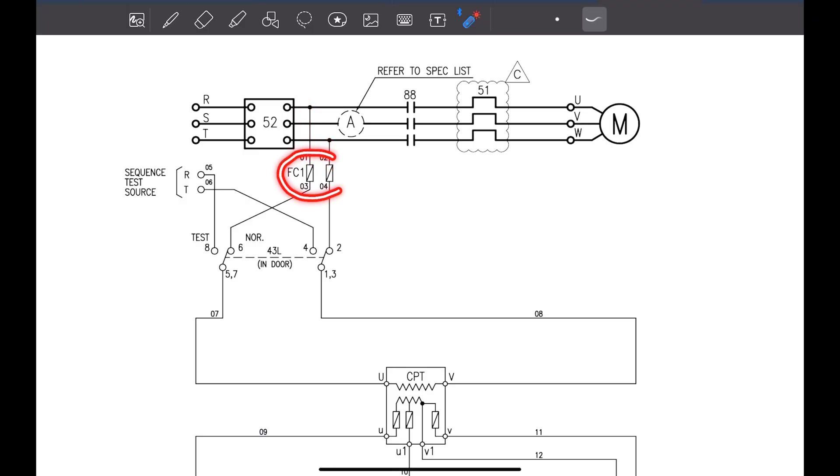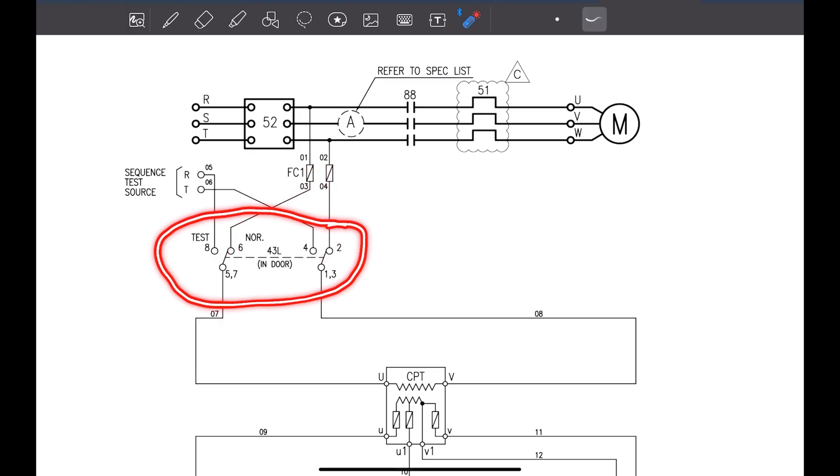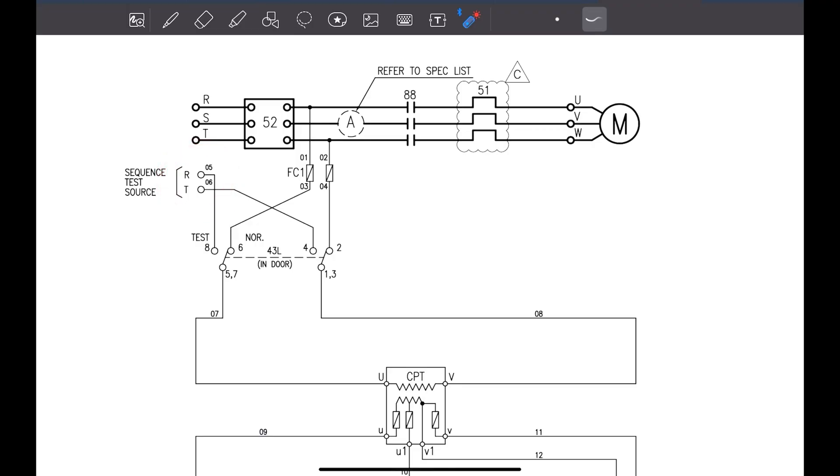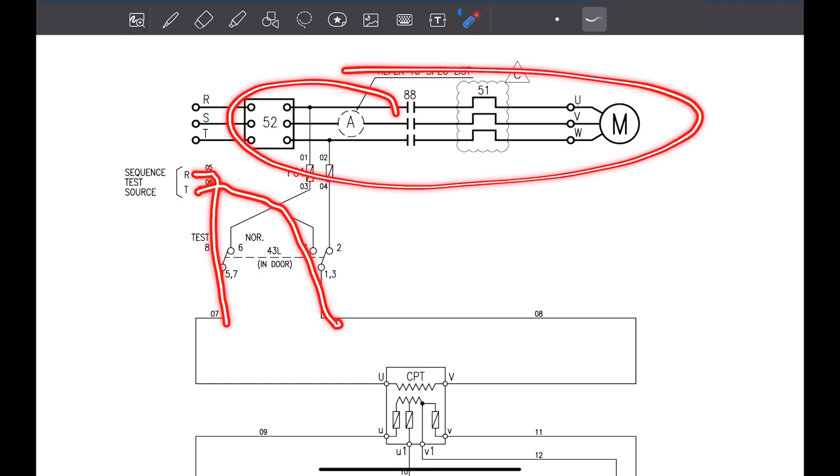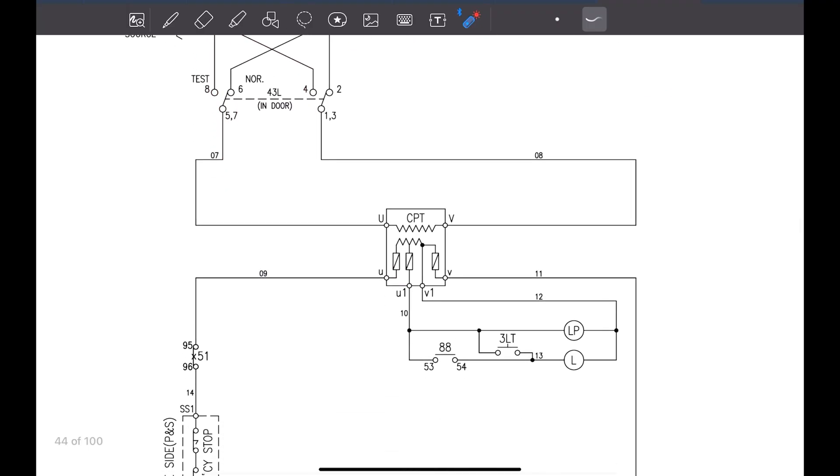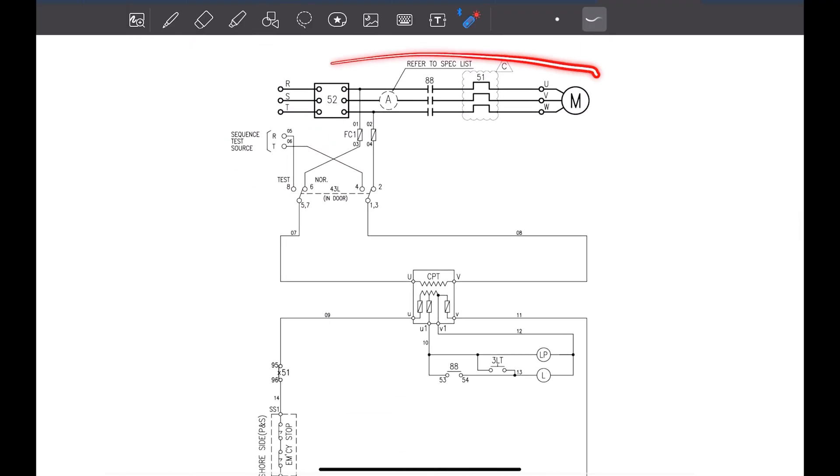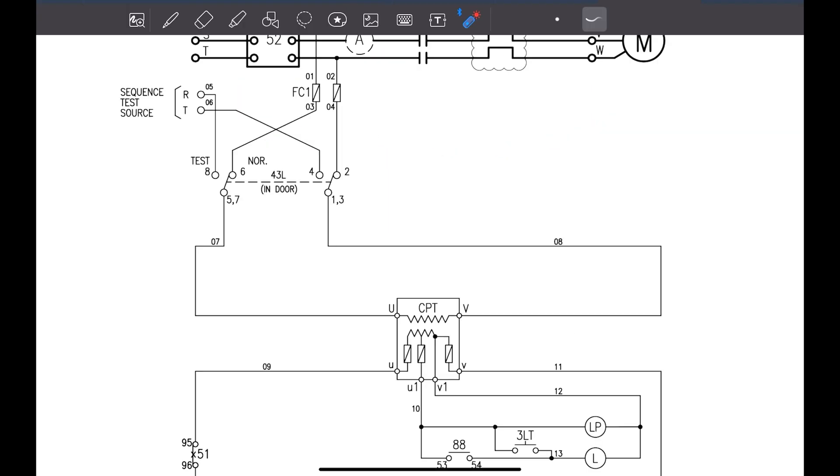Here two points coming to the control part. There is a fuse in both the line. There is a selector switch here. Why this selector switch is here? It is not there in all the ships or it may not be there in all the circuits. But good companies put this. Selector switch is for testing only the control circuit. Suppose I want to test whether my circuit is working or not. But I don't want to power the motor. I will switch off from here. Then I will select the selector switch in test mode. For test circuit power is coming from some other place. If I am selecting the test switch then power will come from here and here. This part will be eliminated from the power circuit. This will be off. When we are switching on from here only the control circuit will be working. The motor will not start in that case.